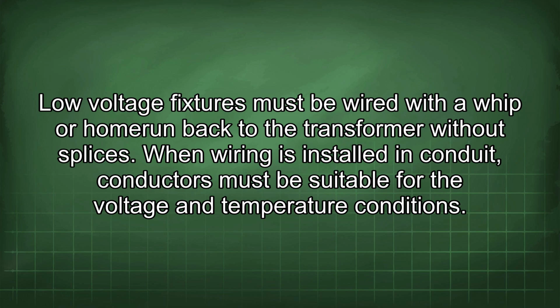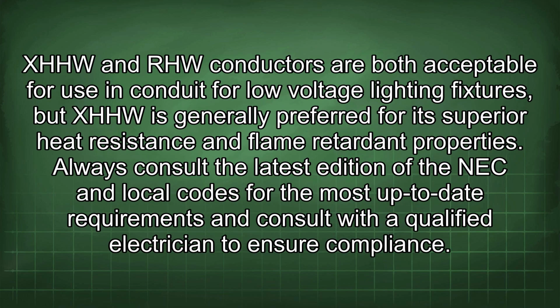Low voltage fixtures must be wired with a whip or home run back to the transformer without splices. When wiring is installed in conduit, conductors must be suitable for the voltage and temperature conditions. XHHW and RHW conductors are both acceptable for use in conduit for low voltage lighting fixtures, but XHHW is generally preferred for its superior heat resistance and flame retardant properties. Always consult the latest edition of the NEC and local codes for the most up-to-date requirements and consult with a qualified electrician to ensure compliance.